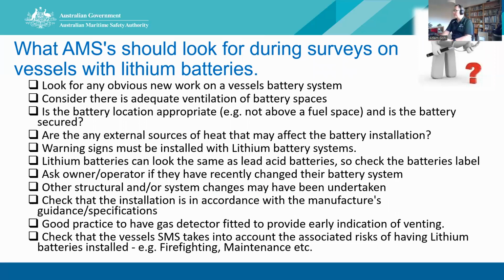Warning signs must be installed. Lithium batteries can look the same as a lead acid battery, so check the labels. Ask the owner operator if they've recently changed the system. Other structural or system changes may have been undertaken to enable them to do that. Check the installation is in accordance with the manufacturer's guidance specs.